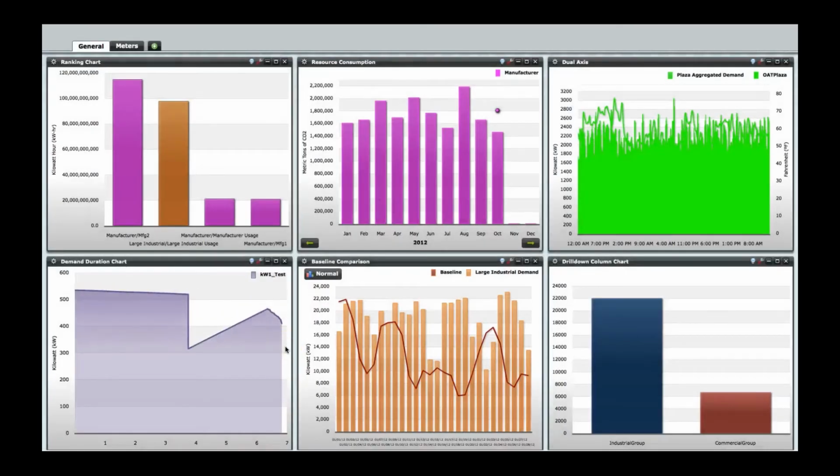This is a very different load profile. You can see that they stay around 3.6 megawatts most of the time, which would translate into a lower capacity charge.